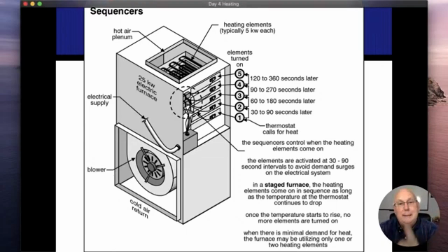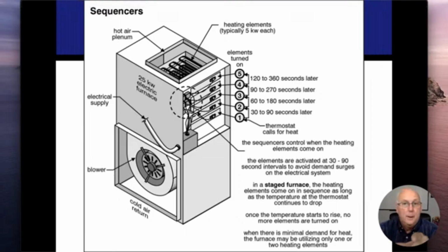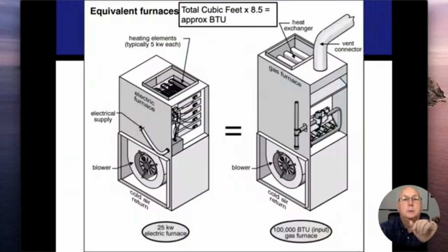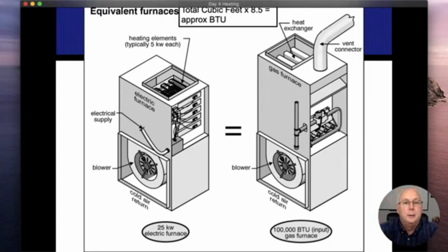All right. One thing that is different about the electric forced air furnaces, these we do change the flow of air. So if I go back a slide, oops, I went too much. The gas furnace on the right: filter, fan, heat exchanger, air conditioner. With the electric furnaces, we're actually going to put the air conditioners before the electric furnaces. So the air conditioner comes first, then the filter, then the fan, and then, I take that back. First it's the filter, then the air conditioner, then the blower fan, and then the heating coils. These are thicker and they're just not worried about being damaged from the air conditioning unit.